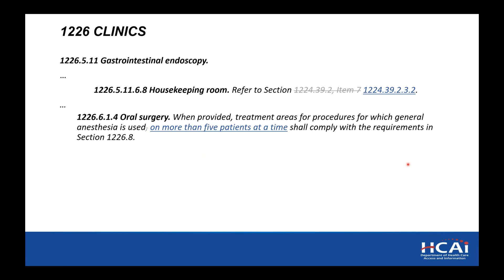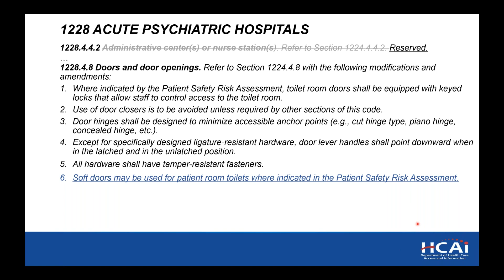Jumping to psych units now, we've actually made a few changes to psych units to make them less in alignment with acute care hospitals, just because the equipment requirements are different. One of the things we're adding is that soft doors can be used for patient toilet rooms. This is specifically the toilet rooms off of the patient rooms, but it must be indicated in the patient safety risk assessment. And these soft doors are collapsible doors so that they're anti-ligature.